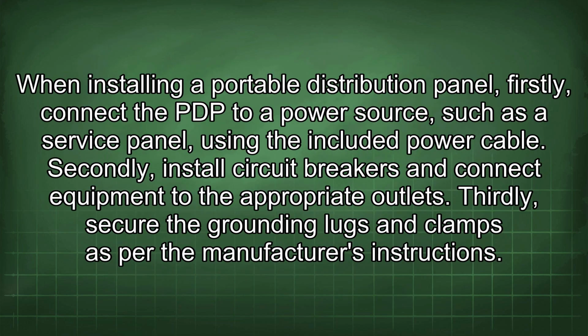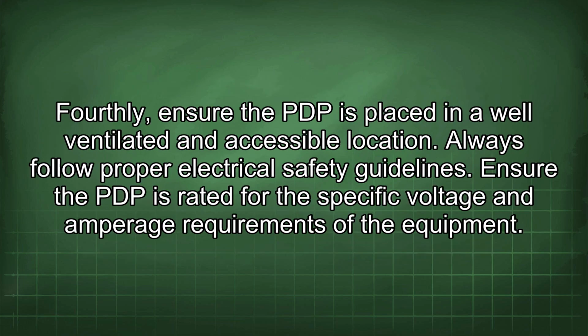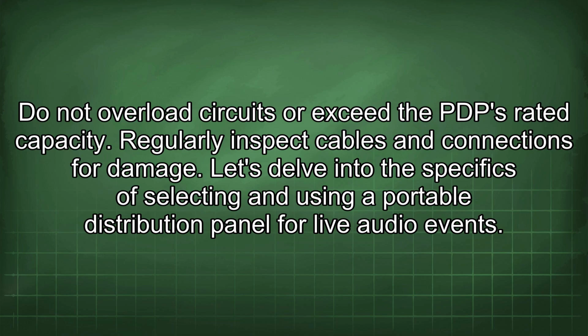When installing a portable distribution panel, firstly connect the PDP to a power source, such as a service panel, using the included power cable. Secondly, install circuit breakers and connect equipment to the appropriate outlets. Thirdly, secure the grounding lugs and clamps as per the manufacturer's instructions. Fourthly, ensure the PDP is placed in a well-ventilated and accessible location. Always follow proper electrical safety guidelines. Ensure the PDP is rated for the specific voltage and amperage requirements of the equipment. Do not overload circuits or exceed the PDP rated capacity. Regularly inspect cables and connections for damage.